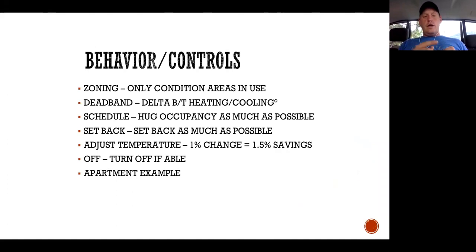But for every degree you adjust your temperature, you can save 1.5% on the HVAC portion of your bill. So adjusting from 72 to 74, or vice versa on heating, actually makes a large impact. And back to the deadband, I would recommend a 5 to 6-degree deadband, not a 2-degree deadband.